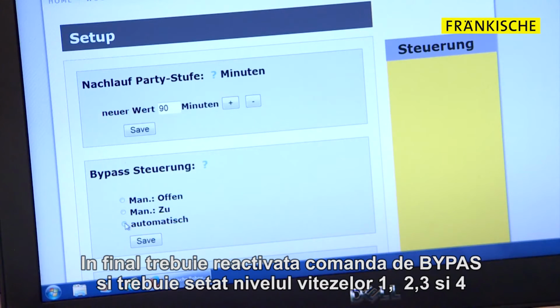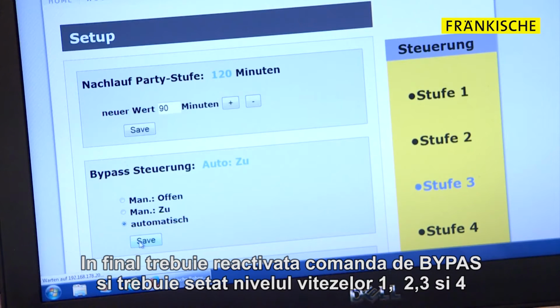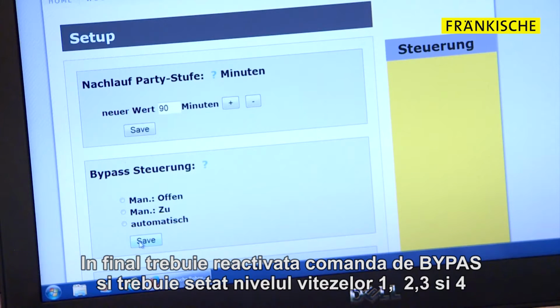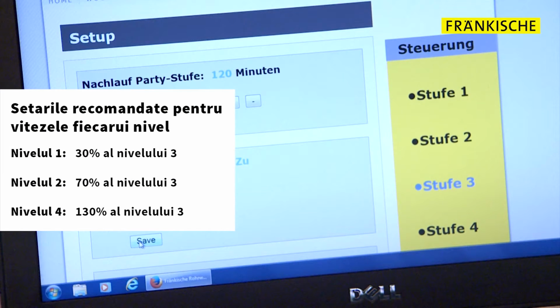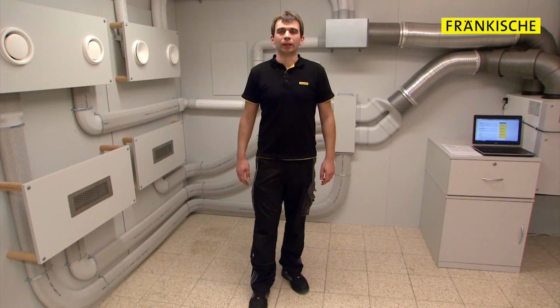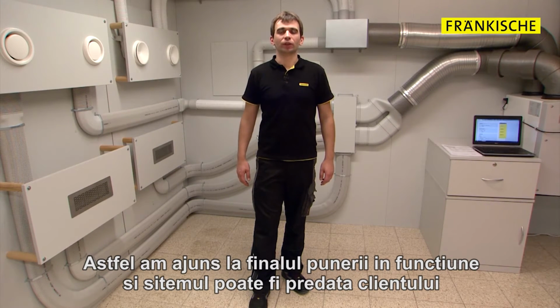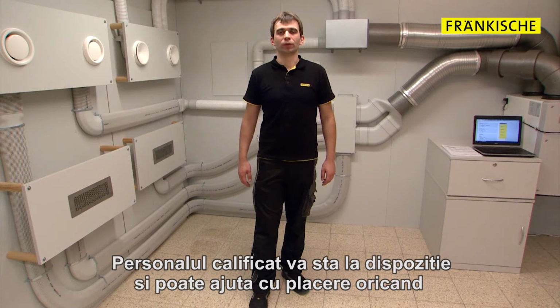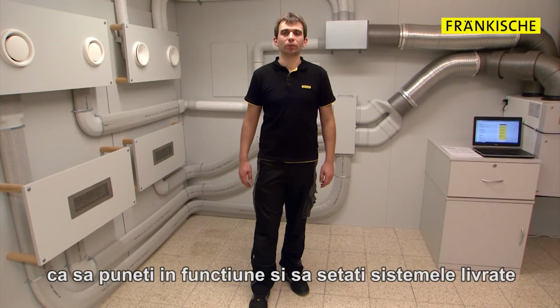Finally, the bypass in the control unit must be reactivated, and the airflow volume rates must be set to fan speed levels 1, 2, 3 and 4. Commissioning has now been completed, and the system can be handed over to the customer. Our qualified personnel will be pleased to help you with the commissioning on site.